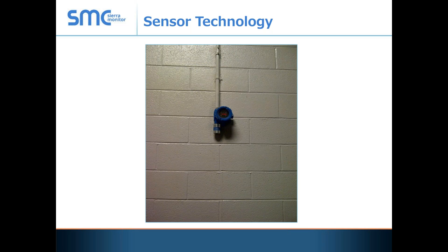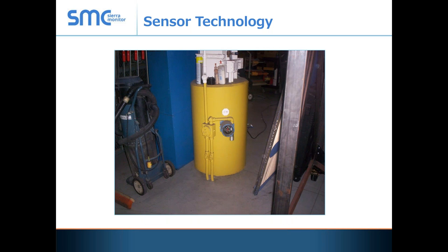Here's an actual CO sensor located about six feet off the ground, to give you an idea what a CO sensor might look like. Here's a sensor mounted in a facility handling LNG — this one is mounted down low. Because of liquefied natural gas, when it's in liquid state it will hit the ground and immediately turns to gas. So the approach was to have at least 20% of exhaust and sensing at that low level. The sensing has since been discontinued there, but the 20% exhaust at that level is still maintained. For that jurisdiction, that's what the fire department decided they wanted.